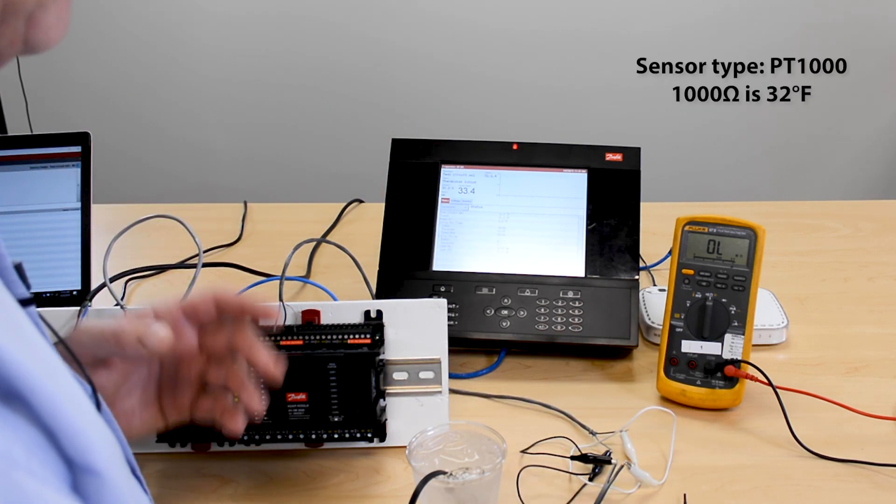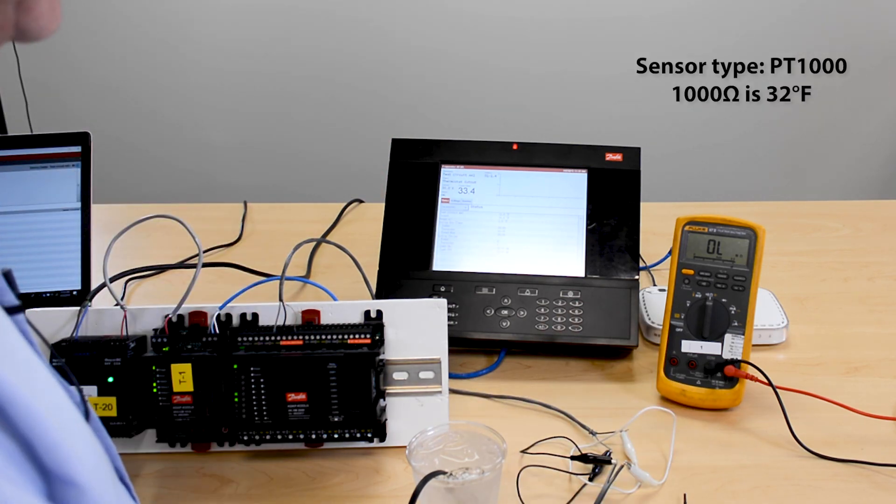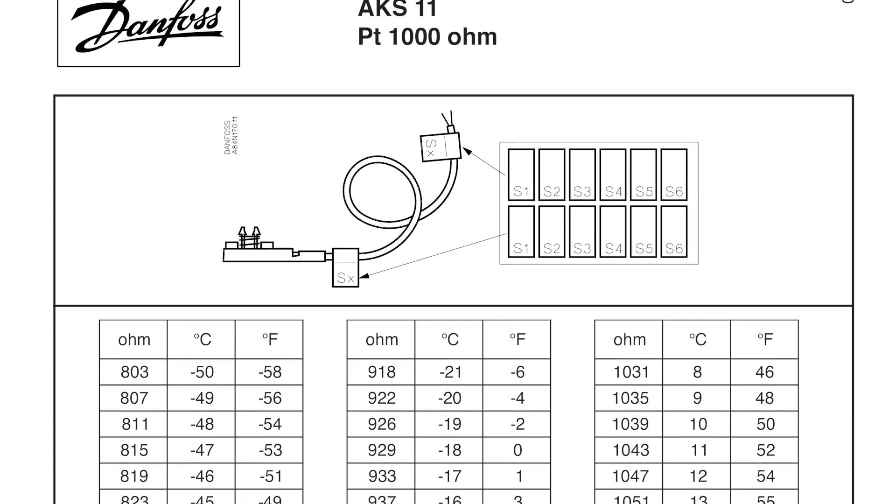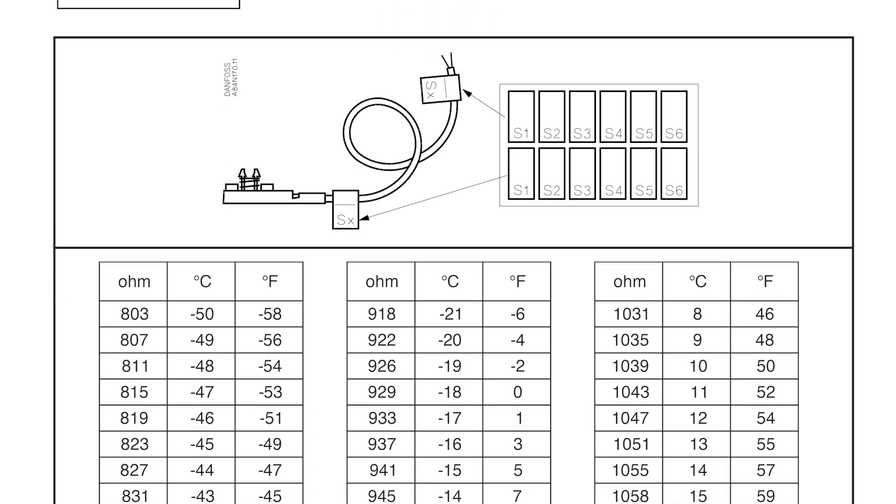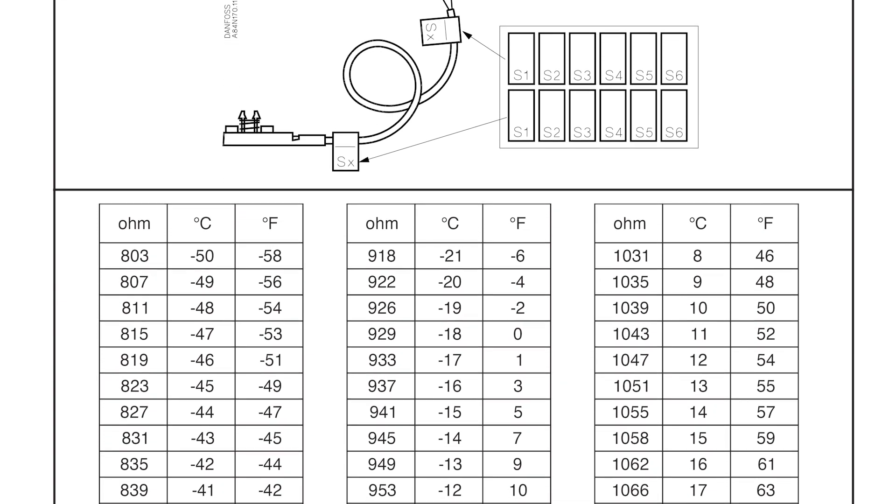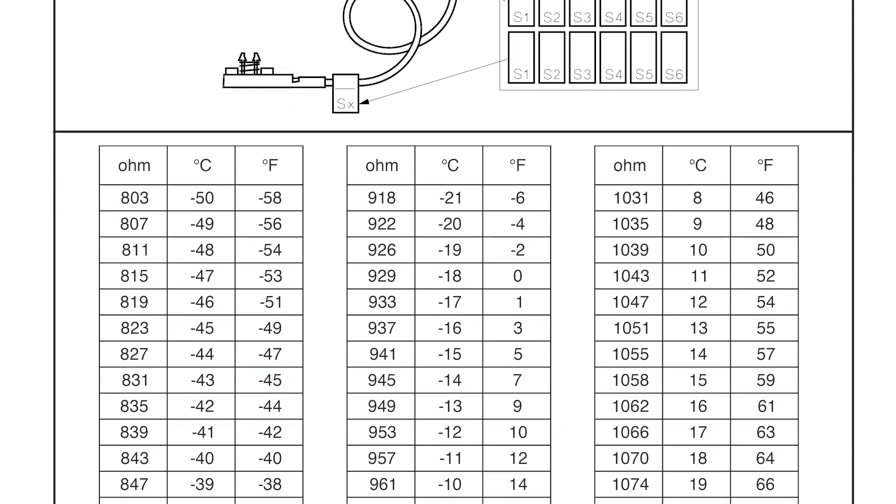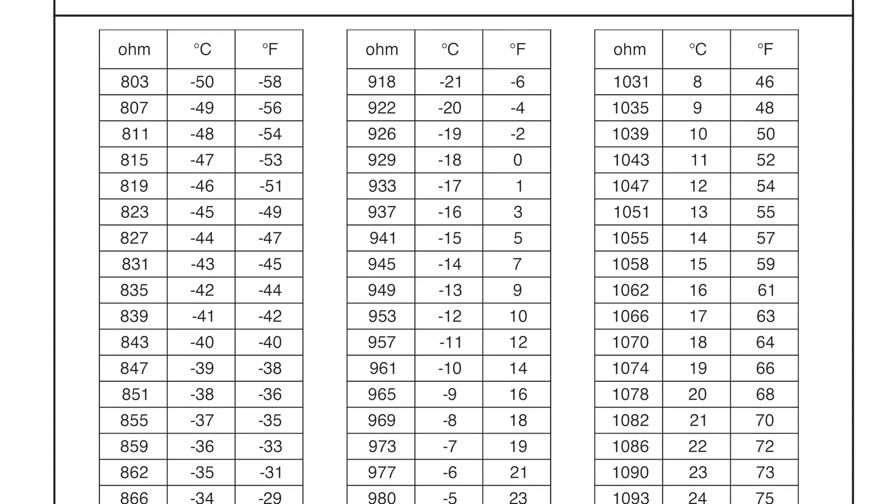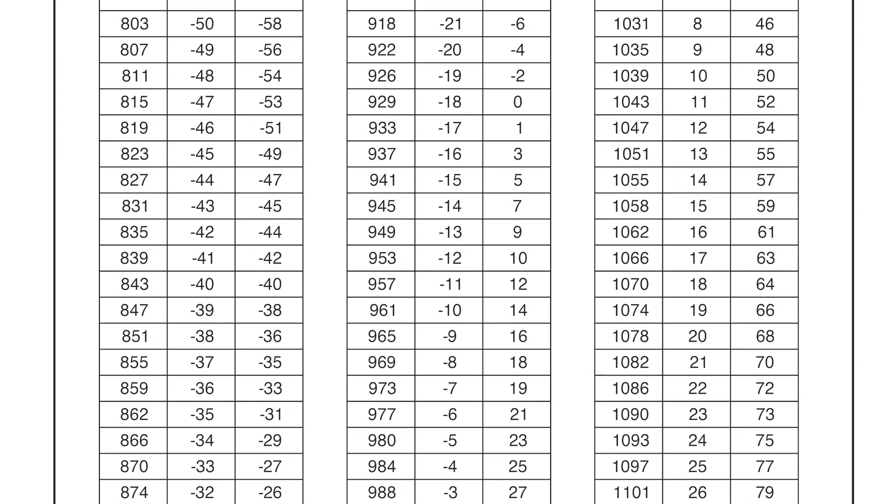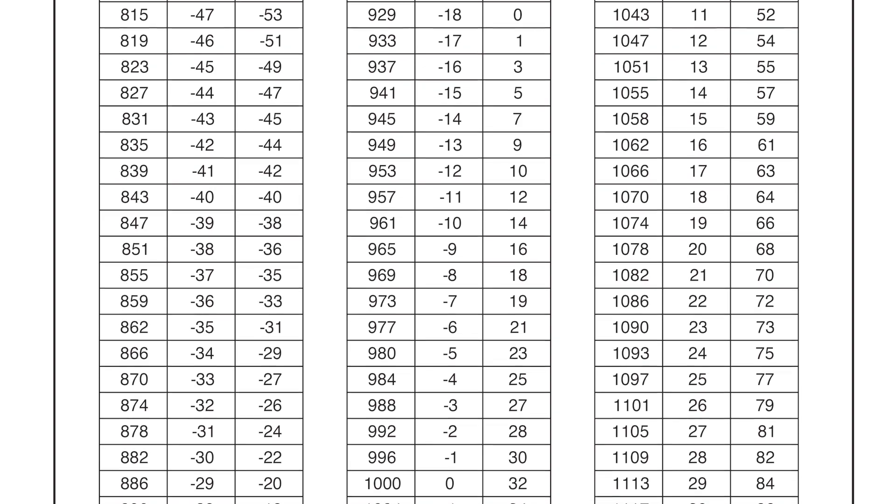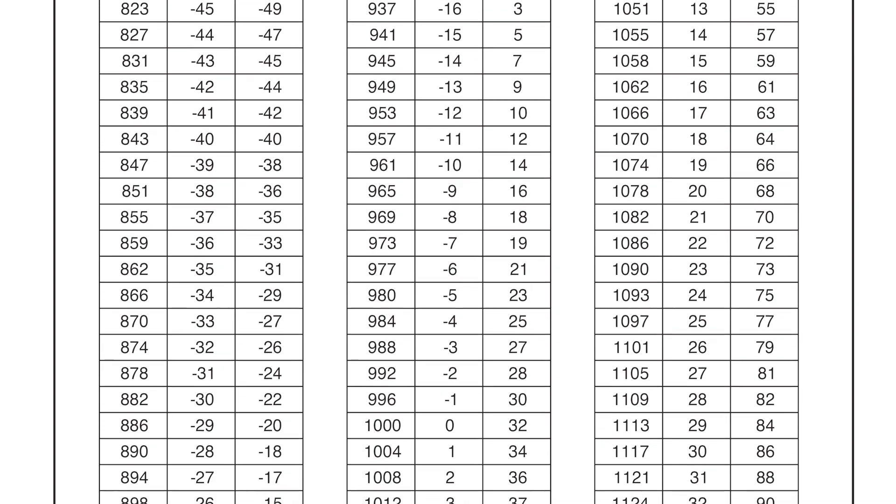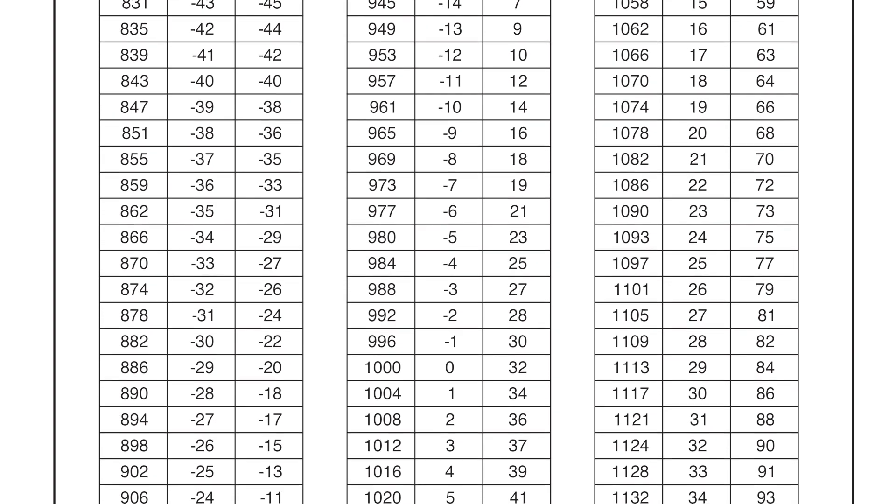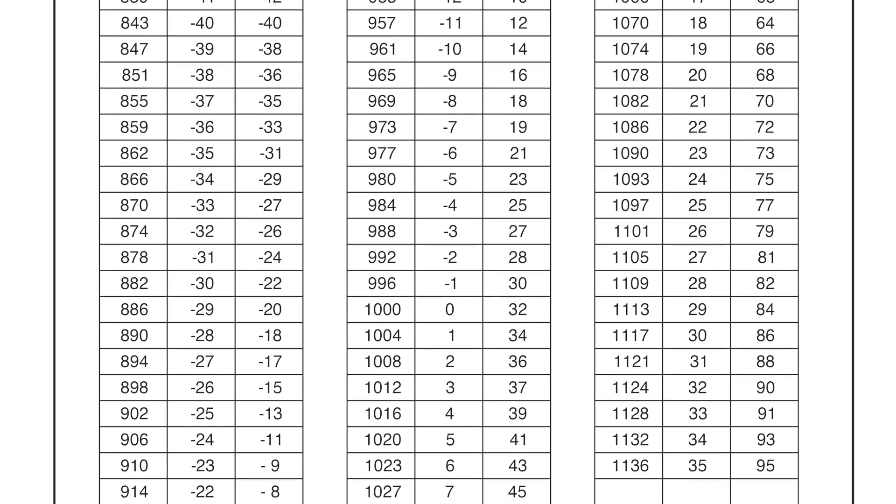As a package we can very easily troubleshoot to find out the status of our sensor. As you can see on the chart, we work in a range from minus 58, which is 800 ohms, up to 95 degrees, which is 1136 ohms. The sensor is a PT 1000, so 1000 ohms equals 32 degrees. If you wanted to reference a low temp application of close to minus 10, you would be about 910 ohms.